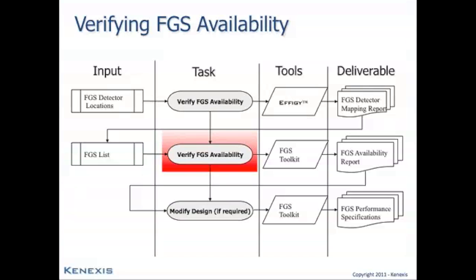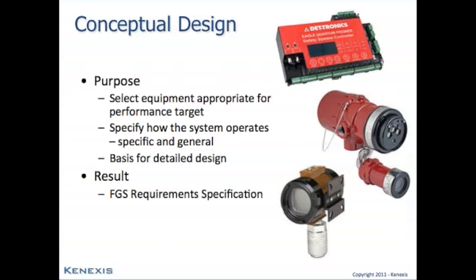This safety availability calculation is very similar to the SIL calculations. In fact, it's identical to the SIL calculations that are performed for safety instrumented systems. When you define a fire and gas function, an FGS function, you begin with a conceptual design that the designers believe will achieve the specified safety availability target.